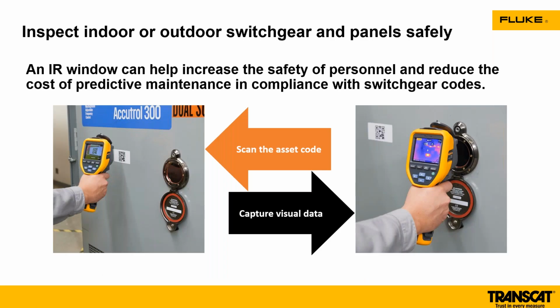Now, we talked about opening up those panels and seeing that load. You can put in an IR window. It's a device that's specifically designed for thermal imagers. A thermal imager will not look through glass or anything of that nature. It'll reflect back. If anybody's seen the Matrix movies, you can look at the lens of one of the agents, and literally that's exactly what it looks like. You just can't see through that glass. So these IR windows do allow you to do that. And how safely? The cabinet's closed. You don't have to put your PPE on. All we have to do is roll back the door cover and do a visual scan. Another key win. It's keeping you safely out of a potential arc flash blast or an arc fault.